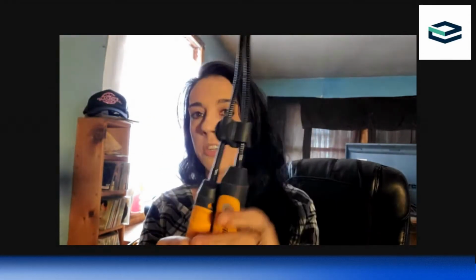And then we have these. These are psychrometers, is what we call them. You guys have heard the term psychrometrics. That's what we use for airflow curves. These are built to measure airflow. So you put one in the supply, one in the return. It will tell you where and what your static pressures are within your systems. Also, they do temperature. So there's that. So these are the tools that we use to check the refrigeration cycle.